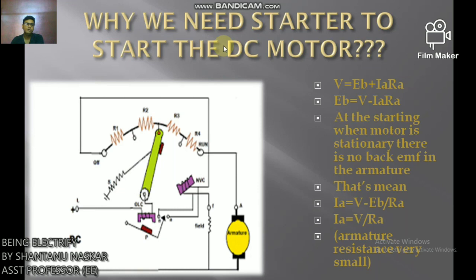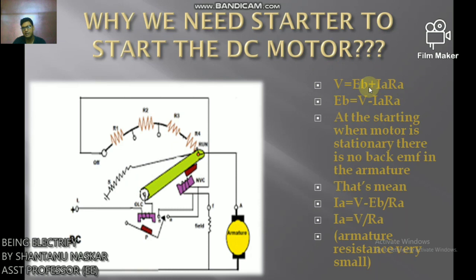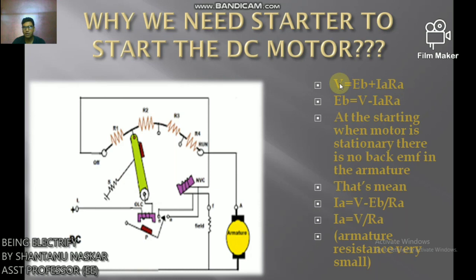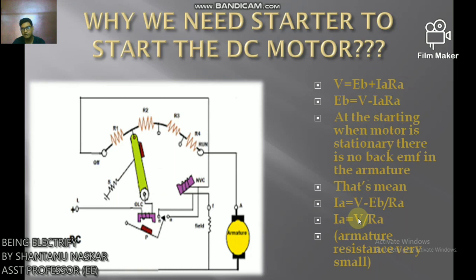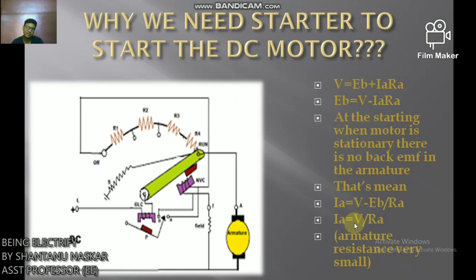First we need to know why we need a starter to start the DC motor. The equation for DC motor is: V = EB + IA × RA, where V is the terminal voltage, EB is the back EMF, IA is the armature current, and RA is the armature resistance. From this, IA = (V − EB) / RA. At starting, when the motor is stationary, there is no back EMF, and armature resistance is very small.